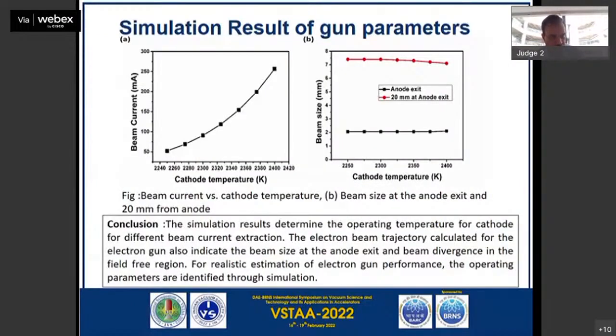Next slide. So 1 minute left. Yeah, I'll come to the last slide where I have generated this beam current graph as a function of cathode temperature. From this graph we can find out at what temperature we would like to operate the gun to extract the desired beam current, and also the beam size. As you can see, the beam size doesn't change when the temperature of the cathode changes from 2200 to 2400 Kelvin. So that's it.